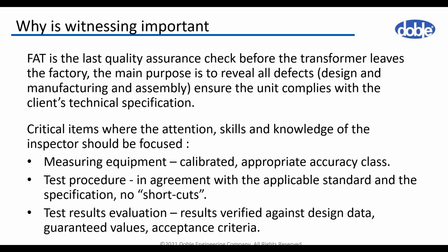This should agree with the applicable standards and specification, and there should be no shortcuts taken during the testing. So practically, during FAT, the manufacturer provides the final results, but it's critical to be sure that the test itself is performed in the correct way, as per the correct standard. Also, evaluation of the test result is very important.